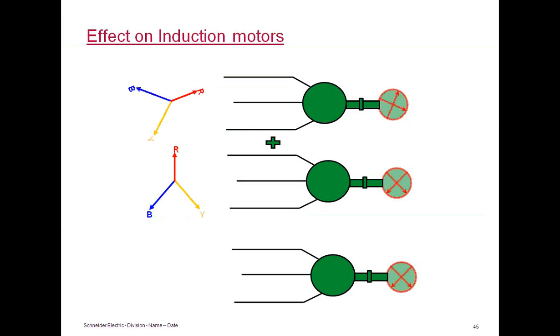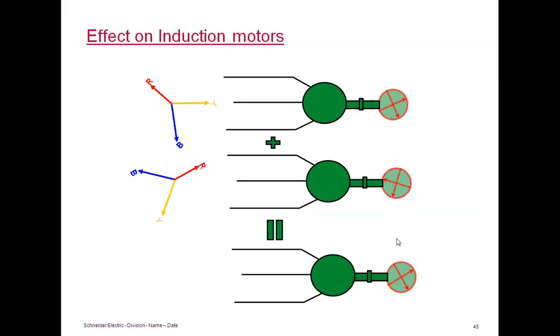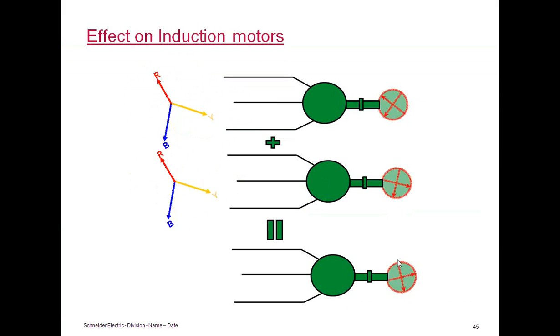If any fifth harmonic is there in the same network where this motor is installed, the fifth harmonic will go into the induction motor, but the speed is 5 times the speed and anticlockwise compared to the fundamental one, and it creates minus torque in the rotor that is transferred to the mechanical load. So the net effect will be low speed. The induction motor will have low speed even though the load has not actually changed. The mechanical load is still there, not modified. So the harmonic tends to reduce the motor speed, because of which the induction motor will try to draw more power just to overcome this negative torque from the harmonics.